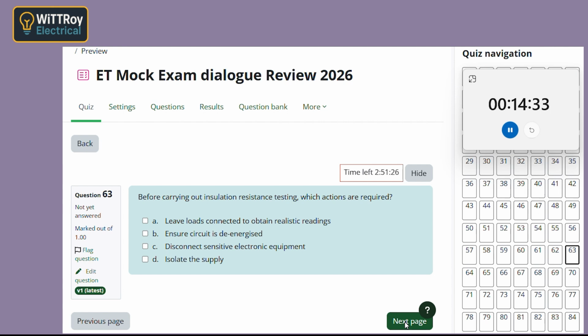Question 63. Before carrying out insulation resistance testing, which actions are required? Isolate the supply, make sure it's dead, and maybe disconnect equipment? Yeah, that's right. Let's just walk through it slowly. When you do insulation resistance testing, you're actually applying a much higher voltage than normal to the circuit. Oh, so it's not just like normal operation testing. Nah, not at all. So if sensitive electronic equipment is still connected, that higher voltage can damage it. Right, so that's why we disconnect it first.